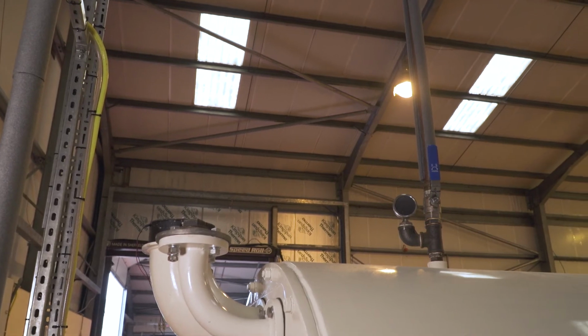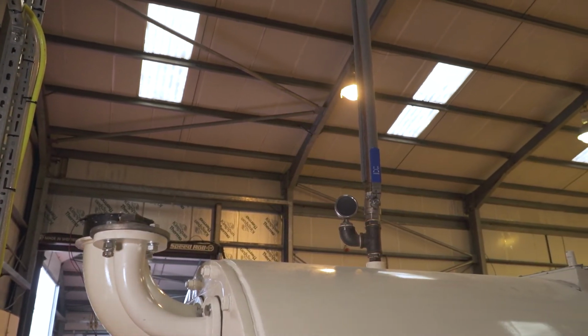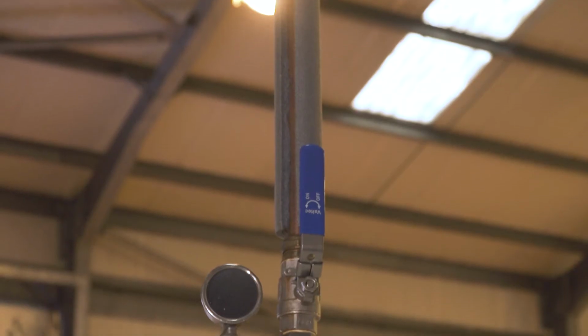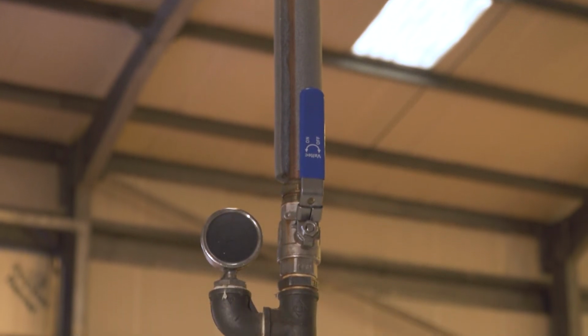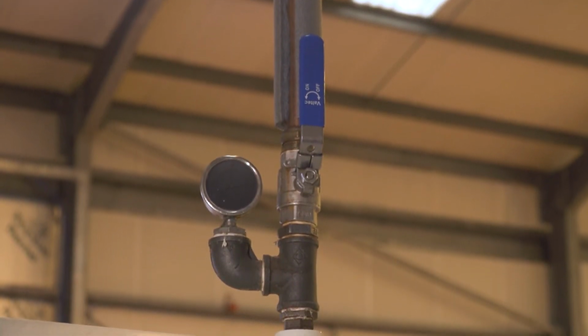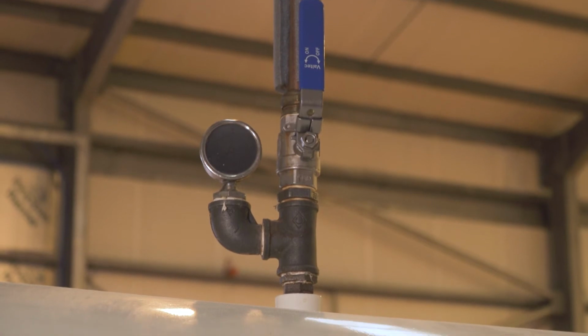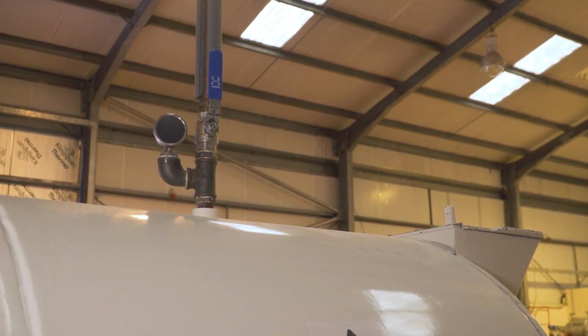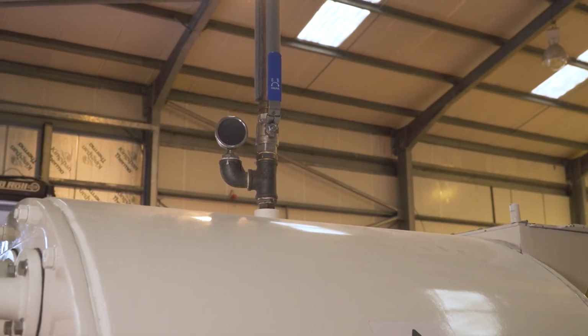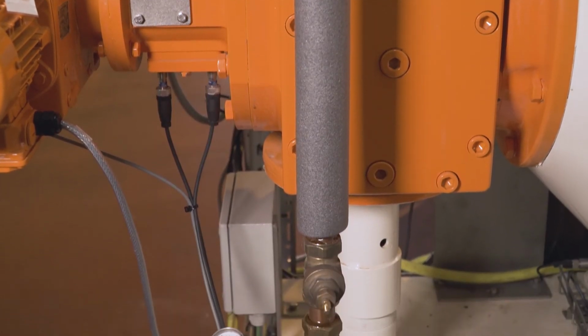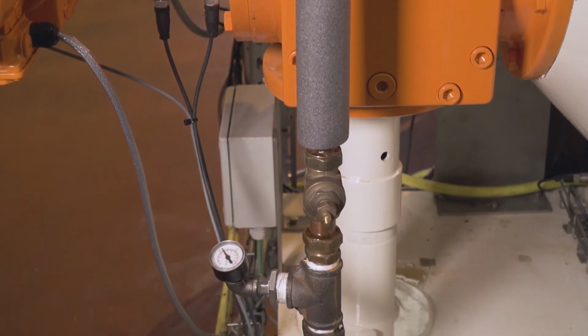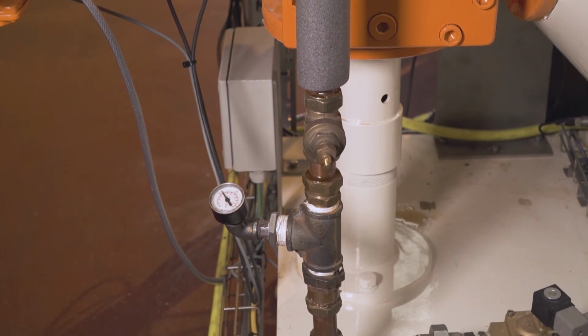In order to keep the product at the temperature of your choice, chilled water will be required. You can talk to a local chiller supplier about the quantity of water needed following the guidelines in the manual, and they will recommend a unit suitable to work with the refiner conch in your environment. Ensure water pressure to the refiner conch does not exceed 1.5 bar.